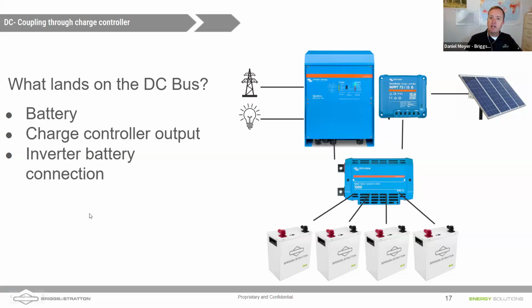So what lands on the DC bus? One of my favorite new products out of Victron is this Lynx Power In - these have Class T fuses in them, and we can bring in our batteries. In this example, we're looking at our Phi 3.8 Briggs Stratton batteries, which are great for lead acid battery replacement. Then we're bringing in our solar through an MPPT charge controller, and landing that all on the DC bus.